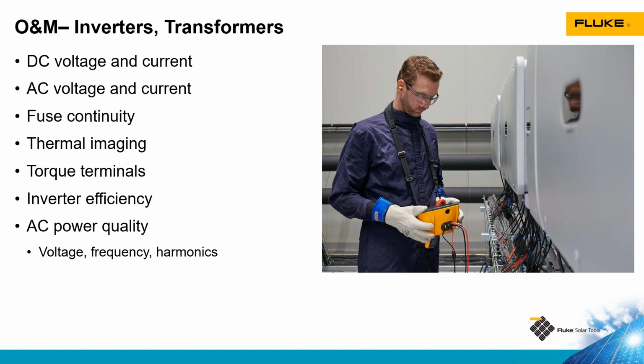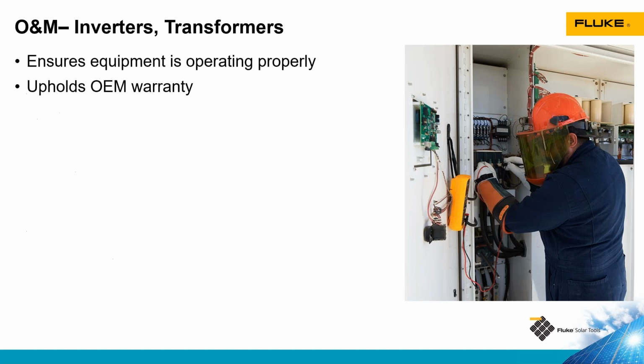Now, in this slide, you've got a technician using the SMFT 1000. And we just want to point out that this is a picture from Europe. They don't use conduit typically there. They use these cable trays. So it's very common to see wires coming out of the bottom of an inverter like we see here. Now, we do our maintenance on our inverters and our transformers because the manufacturer of those equipment has a list of things that need to be done on a regular basis. This is going to make sure that everything's working right.